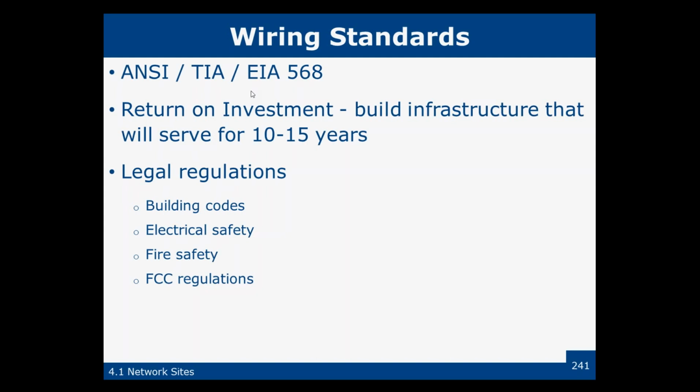Fire safety depends on how you're running the cable. If you're in a plenum, a place where air is transmitted, you have to use plenum cable, and honestly I think most of it is plenum cable today. That includes places like overheads where they just put the air up and it comes down the vents. A lot of buildings are just using the empty space above the false ceilings as the plenum, so you need to be careful.